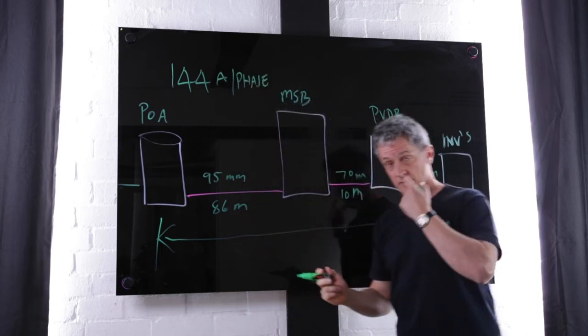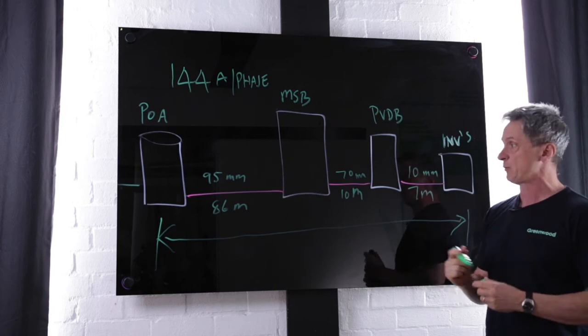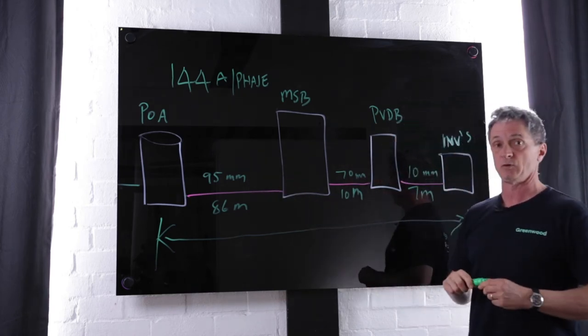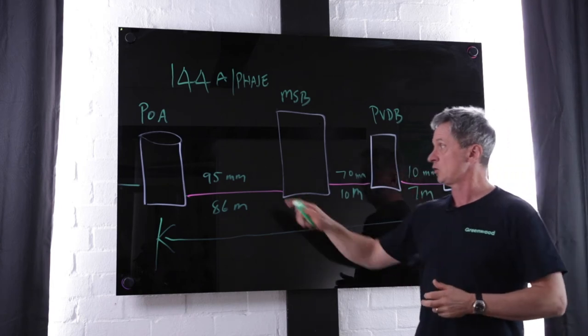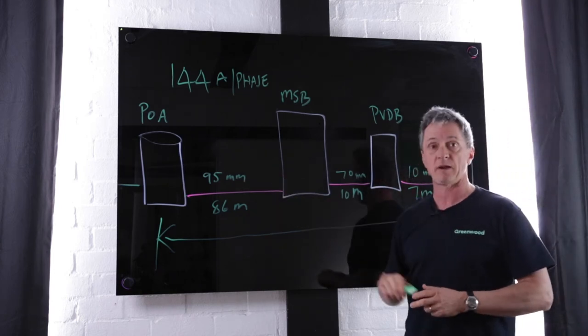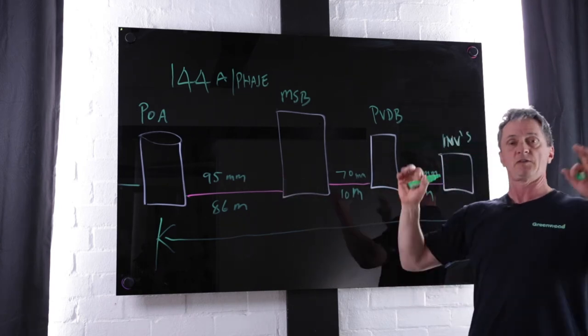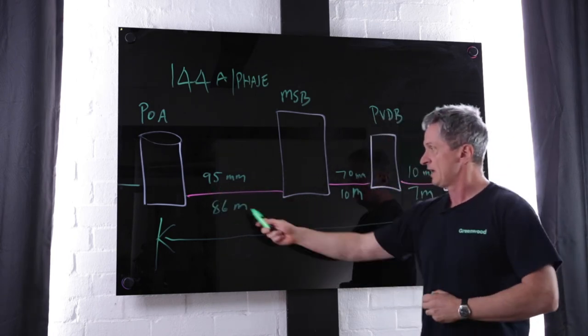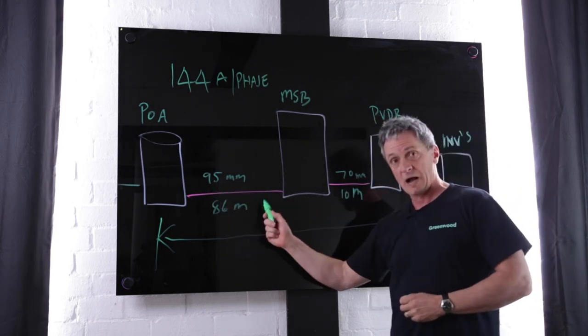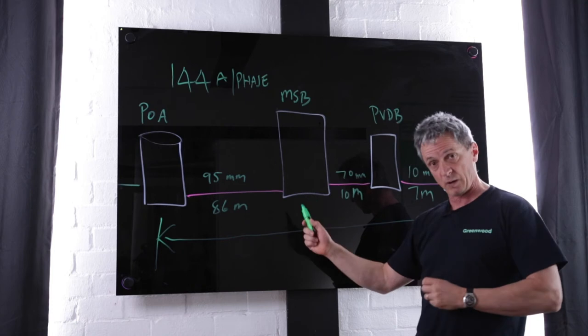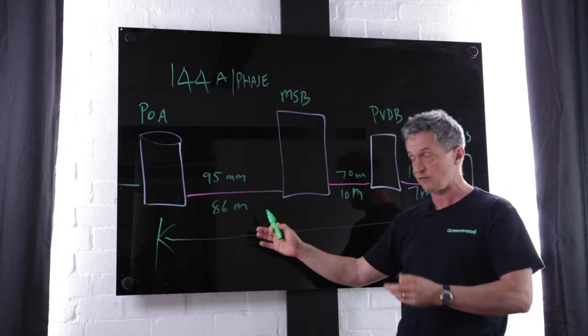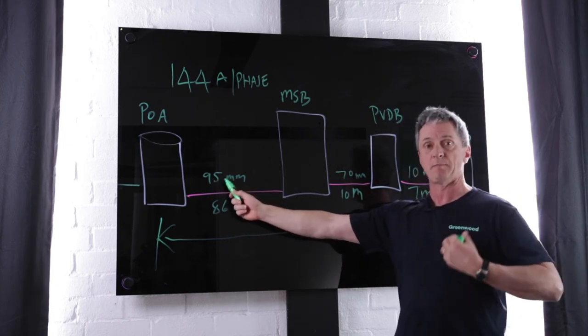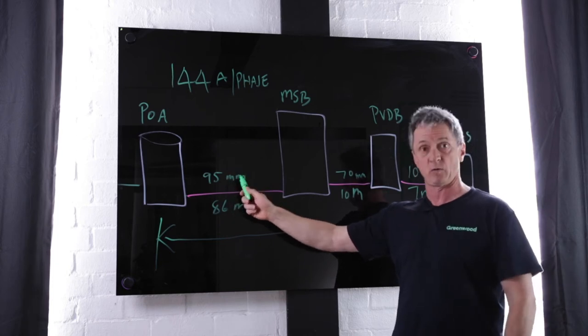From the AS3008 table, we found that the 95mm² cable could carry 217 amps, so no problems on the current carrying capacity of the cable. Then we look at the run of the cable — that's where we do our volt rise calculations — and we also look at the millivolt per amp meter rating of that 95mm² cable.